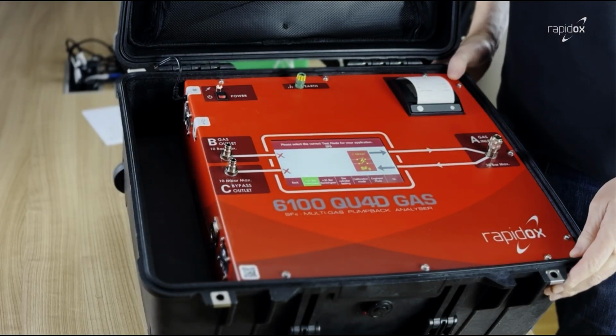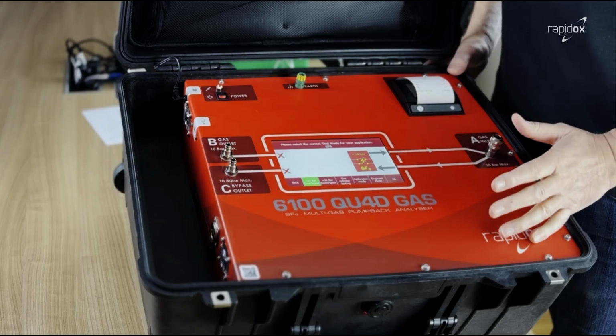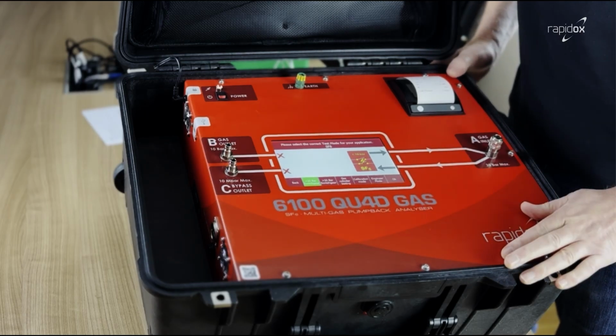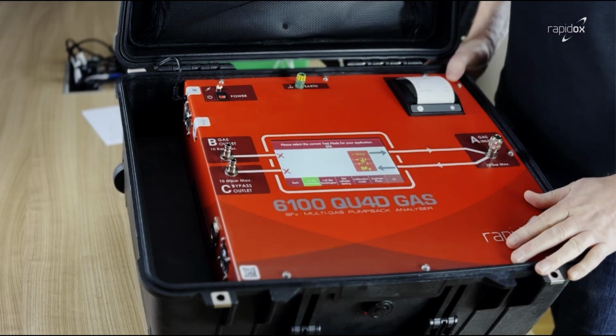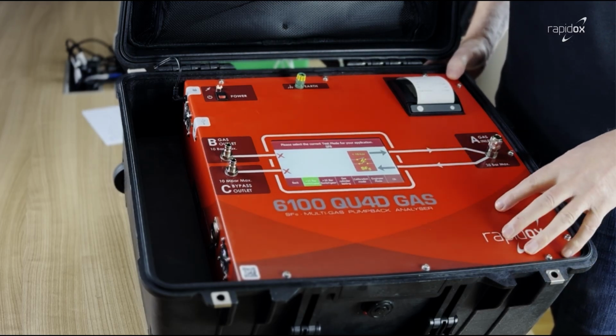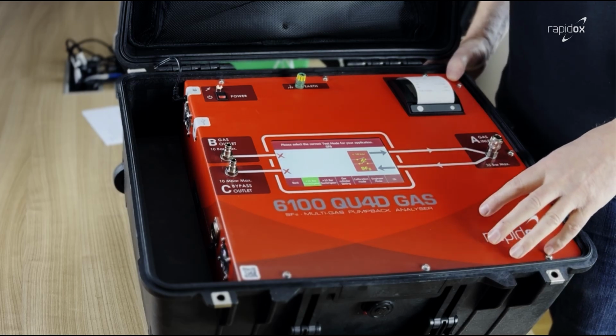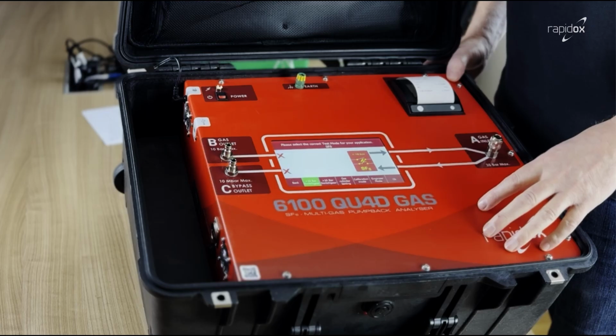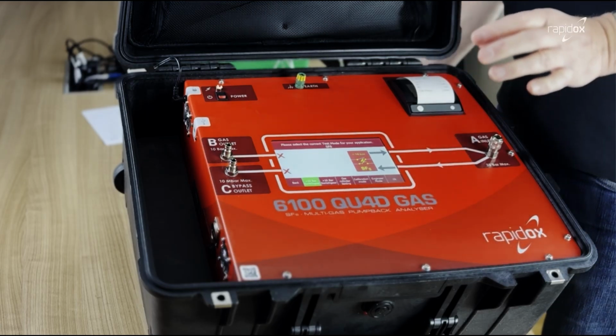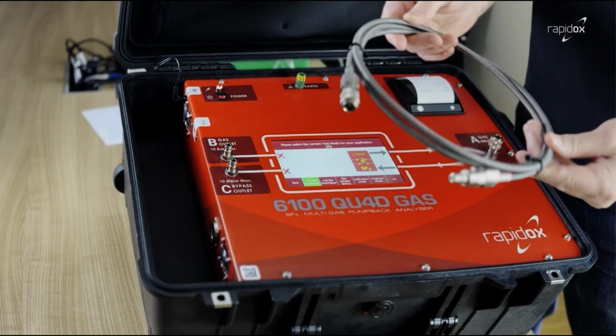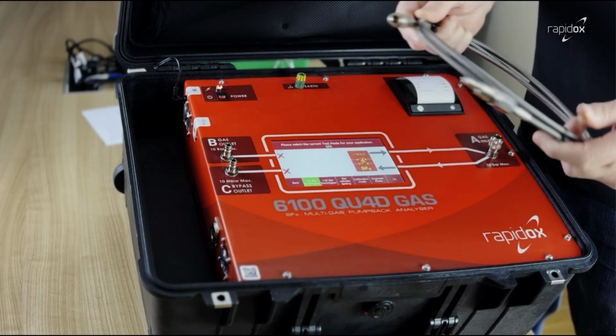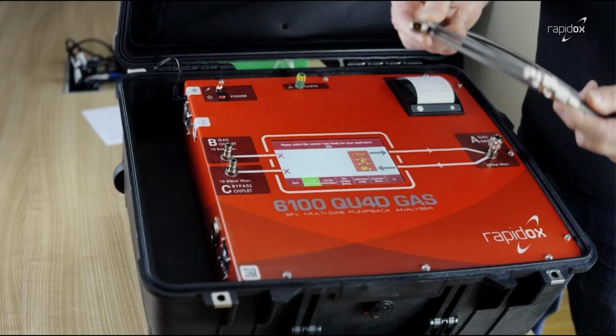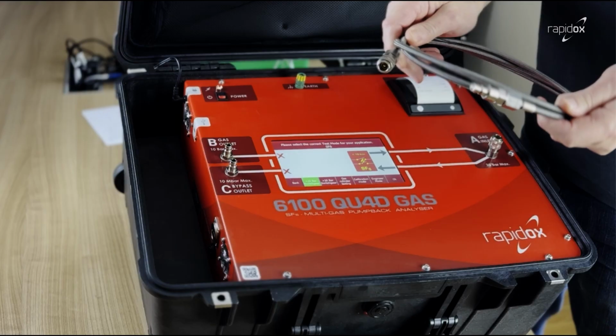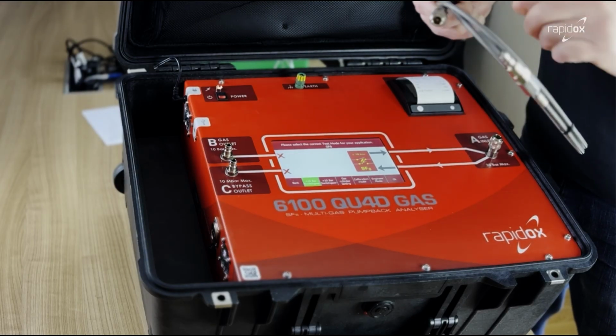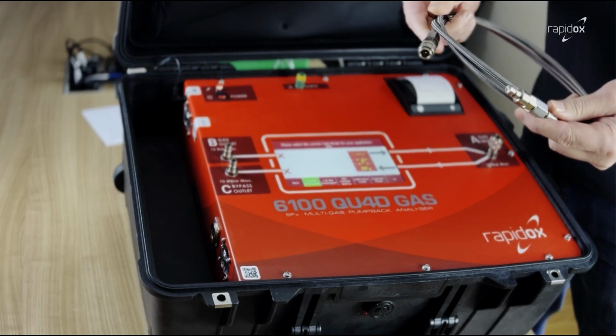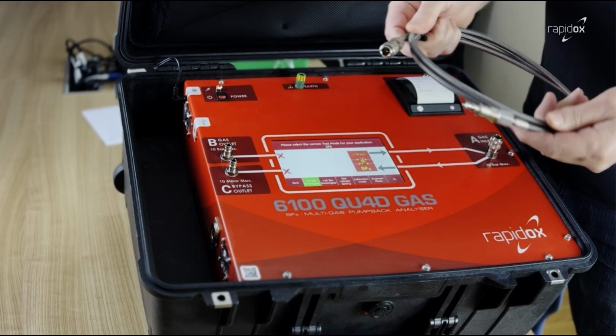I'm now going to talk to you a little bit about the accessories that are supplied with the instrument. So starting with the main hose, and the main hose is extremely important for using this machine. It's specially designed for SF6 and Novec gases, etc. It's manufactured with a special lining to be waterproof. So the hose that's supplied with the machine is a stainless braided Swagelok type hose, and it has Rectus fittings on each end which are compatible with nearly all switchgear in the world, with the right couplings. So these are very highly compatible connectors that are used on many gas analyzers in the SF6 industry and alternative gas industry.